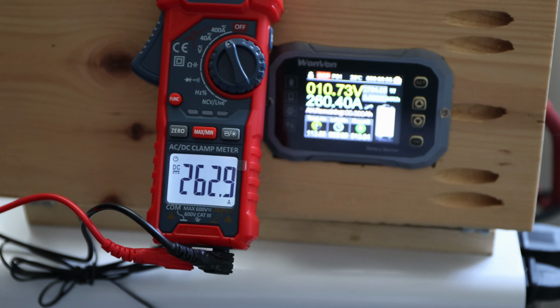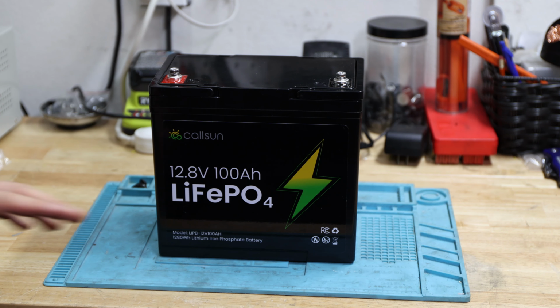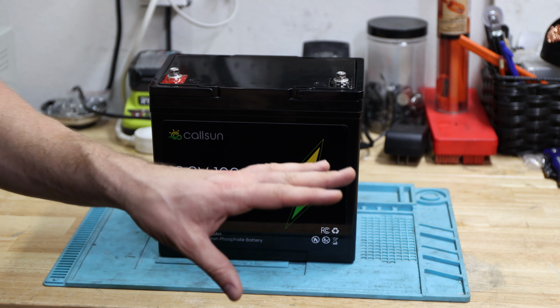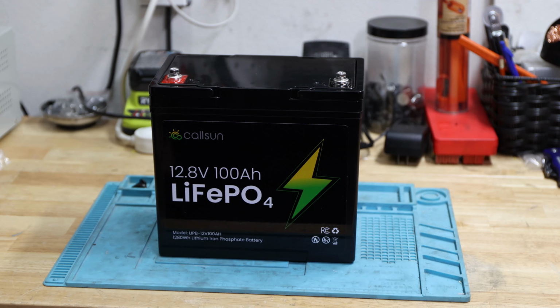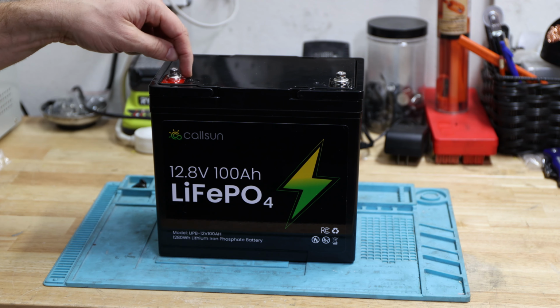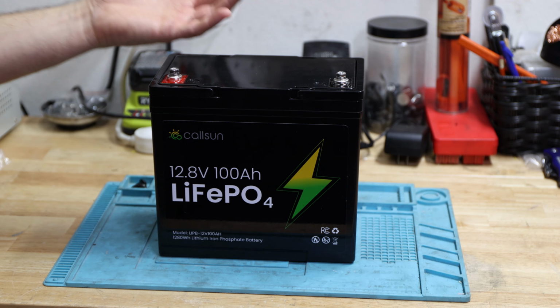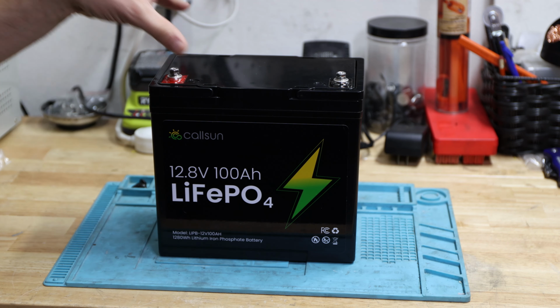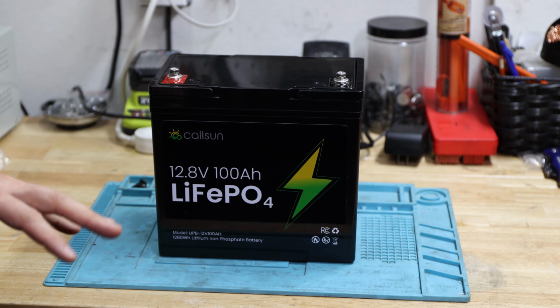Alright, 104 amp hour capacity test, that's pretty good. Also the high discharge test showed definitely more than the advertised maximum continuous discharge of 100 amp. That also means, in terms of overcurrent protection, we're pulling more than 100 amp. It's great in case you have everything set up with your fuse and everything else out there.